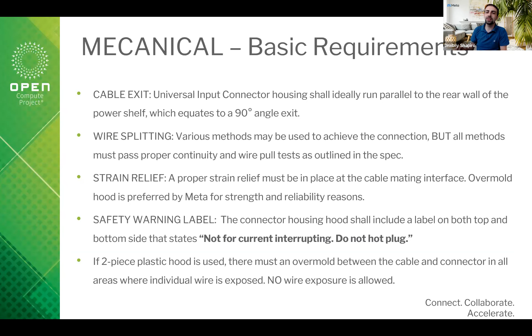For the power cord selection, this was one of the toughest things for this cable, and it also goes off what Will mentioned earlier. For the NEMA cable, it's pretty straightforward. We use the SOW 12 gauge 5C standard. The 5C stands for five wires inside the cable, or an STW. The only difference is one is rubber, one is PVC, but rubber is a little easier to route through the rack.